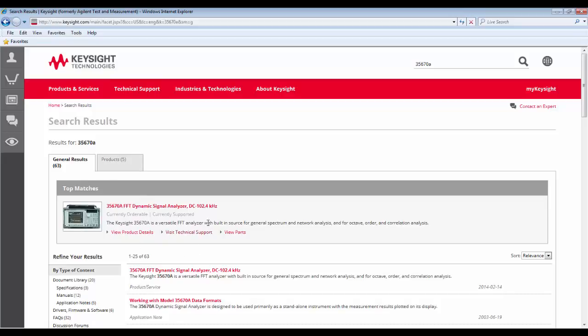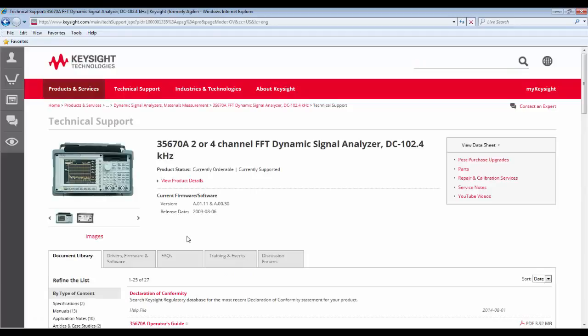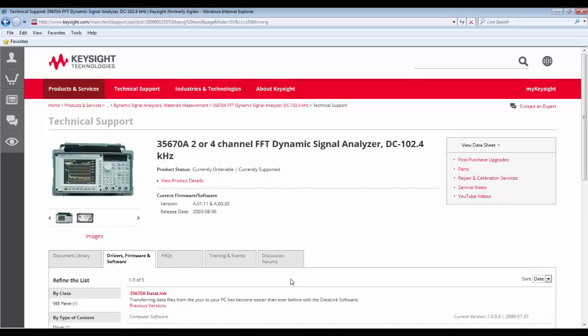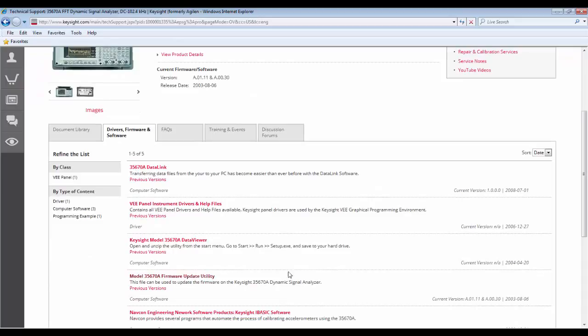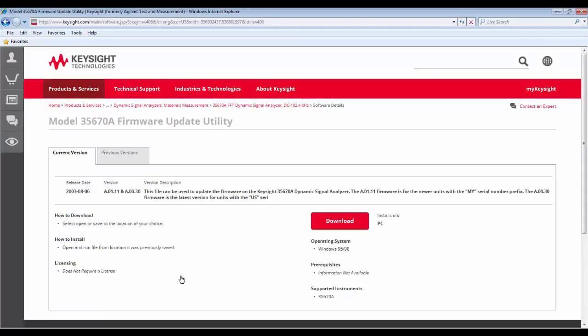Once the top match appears, you will select the Visit Technical Support link and wait for the technical support page to appear. From this page, you'll select the Drivers, Firmware and Software tab and then go down and select the 35670A firmware update utility. This link takes you to the page from which you can download the free firmware. The firmware package contains both the A.00.30 and the A.01.11 versions of the firmware. Within the firmware package, you will also find the instructions on how to create the floppy disks and install the firmware into the 35670A analyzer.